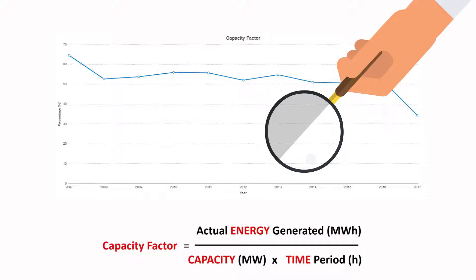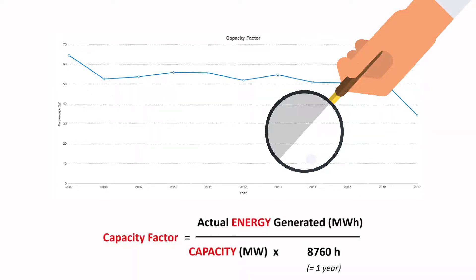Capacity factor is usually expressed as the ratio of the average power generated over a period compared with its maximum output. The common time frame for analysis is either a month, which contains 720 hours, or a year, which contains 8,760 hours.